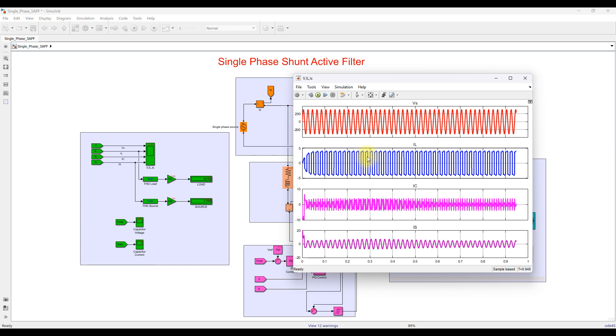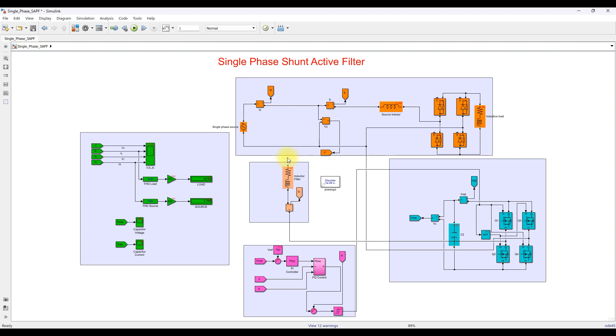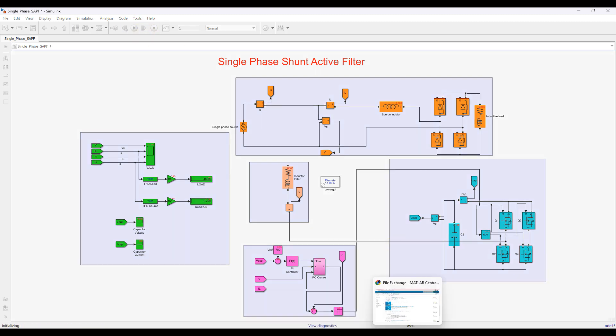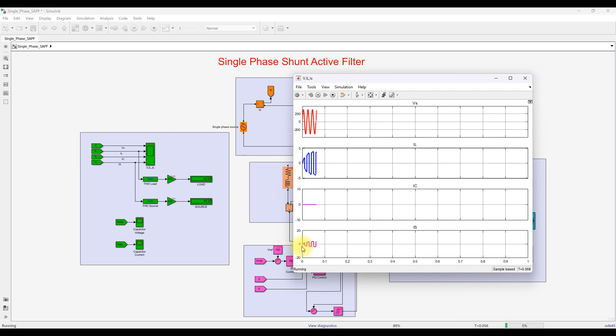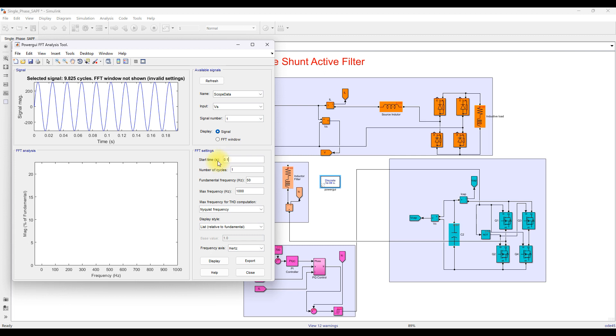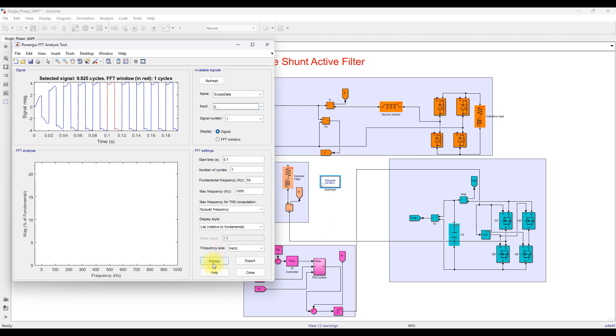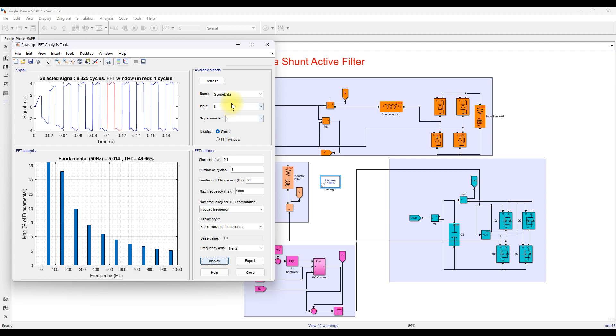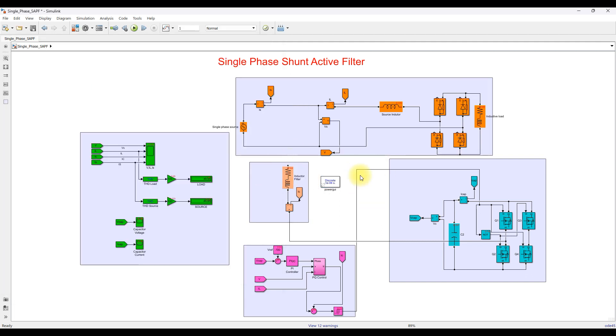To check the result without using the shunt active filter, I will disconnect it from the circuit. Without the shunt active filter connected, you can see that the load current and source current have the same non-sinusoidal nature. Checking the THD now, both the load and source THD are around 46%, because the shunt active filter is disconnected from the system. Now I am going to reconnect it.